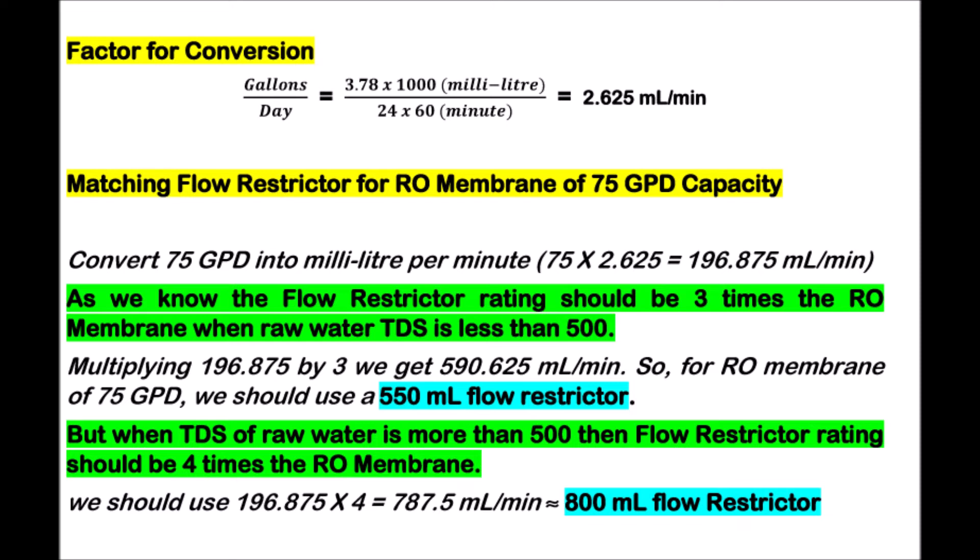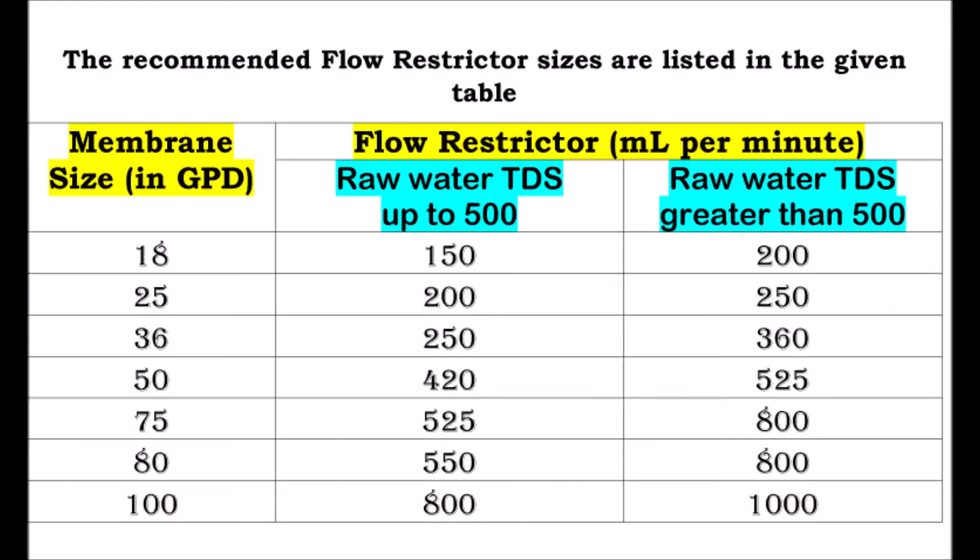But when the TDS of raw water is more than 500, the flow restrictor rating should be 4 times the RO membrane capacity, so we should use an 800 ml flow restrictor. To make it simple, the recommended flow restrictor sizes are listed in the given table.